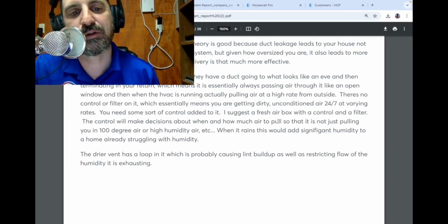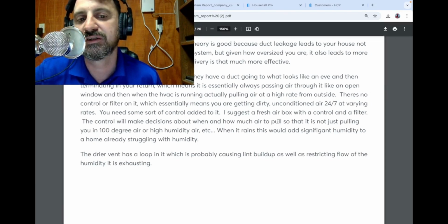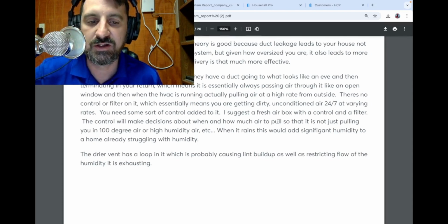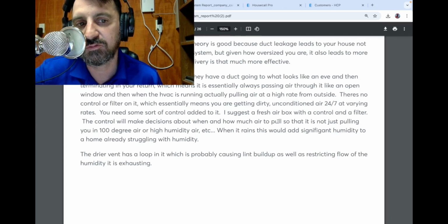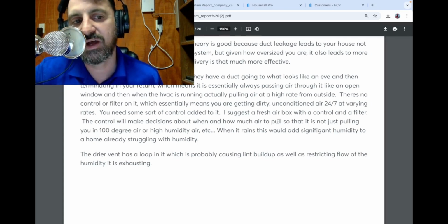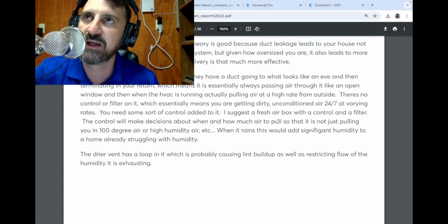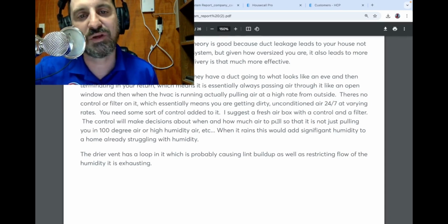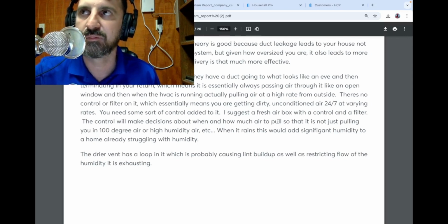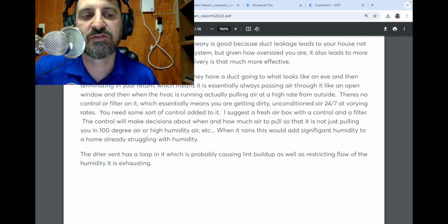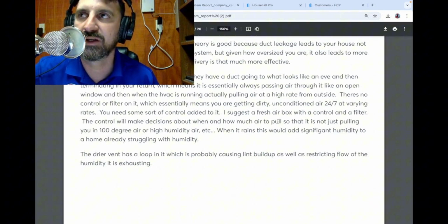I'm suggesting a fresh air box. An ERV is a better solution, but this homeowner wanted an idea of how to best go about it while not hitting all of the high-end stuff. The fresh air box will work similar. It'll have a filter, it'll have a control. So the control will bring in a certain amount of air throughout the day, but it will also make decisions. If it is 105 outside, it'll say, let me wait a couple hours, let that temperature drop, and then I'll bring the air in. Or if it's above a certain percent of humidity outside, it'll say, hey, let's wait a while, bring it in later.